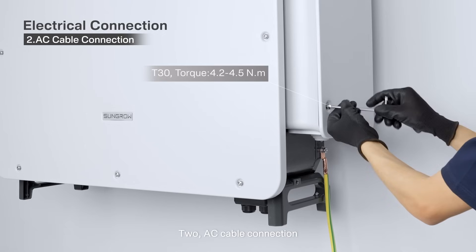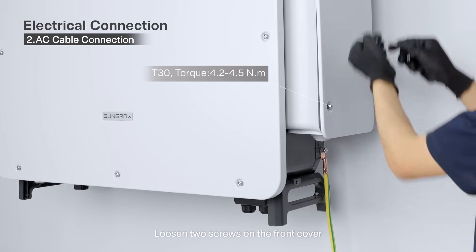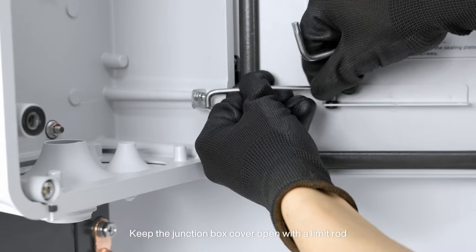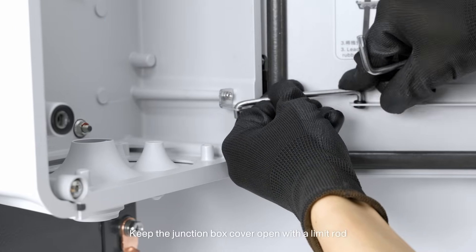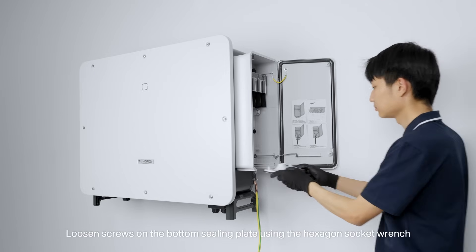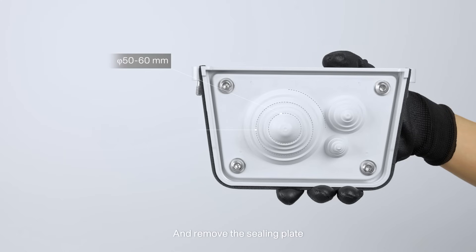2. AC cable connection. Loosen two screws on the front cover of the junction box using the supplied hexagon socket wrench. Keep the junction box cover open with the limit rod. Loosen screws on the bottom sealing plate using the hexagon socket wrench and remove the sealing plate.